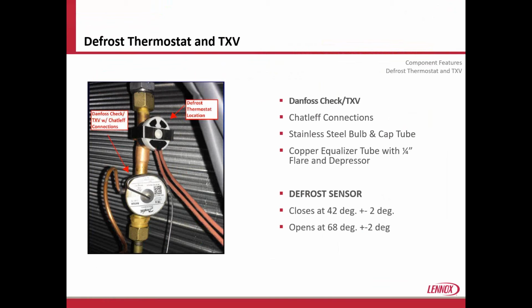So what that means is once a defrost is initiated, it's going to keep it in defrost mode for a maximum of 11 minutes. If the sensor does not remove it, the board will automatically remove it after 11 minutes, or as soon as the sensor reaches 68 degrees, it will terminate defrost and go back into normal heat pump operation. Then at that point, your heaters will stage back down and everything will go back to normal like it was before.